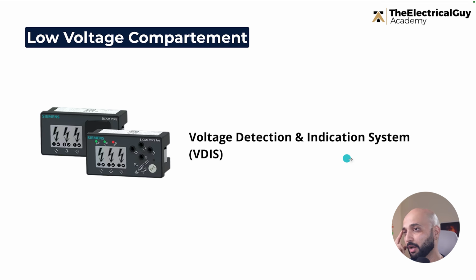And then you will also find the voltage detection and indication system, VDIS. This is very important. You will find it on ring main units and medium voltage switchgear, not mostly on high and extra high voltage switchgear. It's basically a safety system. It checks if there is a voltage on the line side. If yes, you will get an indication on it. This is very important because when you want to carry out maintenance on, let's say, the cable compartment, and if voltage is present there, you should not do that. It's risky. So with this indication, you will get to know whether the voltage is still there or not.